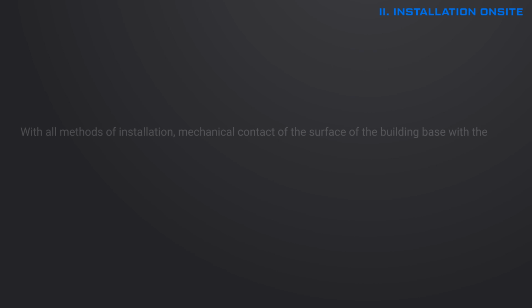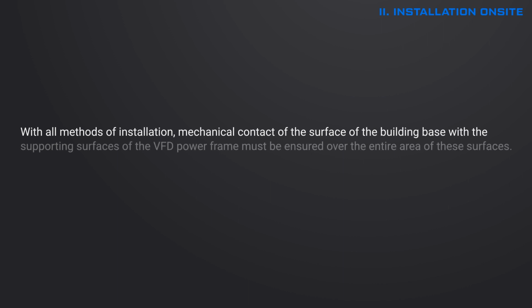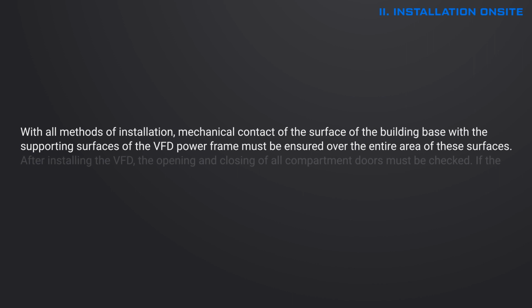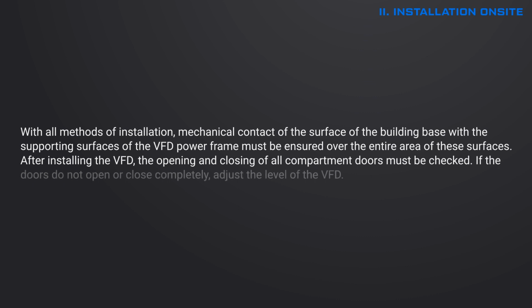With all methods of installation, mechanical contact of the surface of the building base with the support surfaces of the VFD power frame must be ensured over the entire area of these surfaces. After installing the VFD, the opening and closing of all compartment doors must be checked. If the doors do not open or close completely, adjust the level of the VFD.